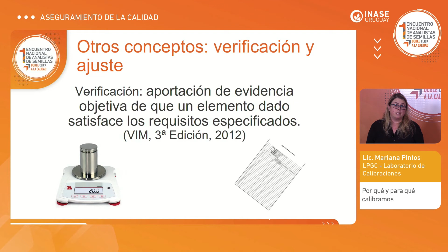There are other concepts that are easily confused with calibration: verification and adjustment. Verification is a provision of objective evidence that a given item fulfills specified requirements. For instance, I verify the scales. I put a weight on the scales and I get 20 grams. Okay. There is tolerance for verification. If it's out of range, then I cannot work, and I need to decide if I need to make an internal adjustment, and the result is good, or maybe I need to recalibrate, repair, whatever.